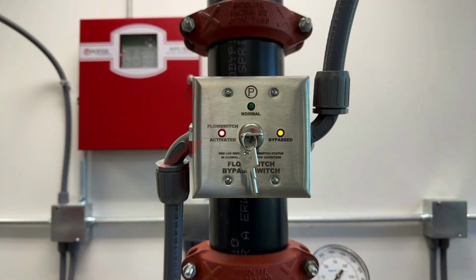The red flow switch activated LED provides a visual indication of the flow switch status in both normal and bypass modes. This helps to prevent unwanted alarms caused by turning the key switch back to the ready position while the flow switch is still activated. It can also be used as a visual indicator to identify which riser is flowing in a normal condition.